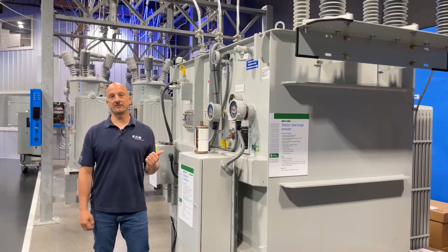So this transformer is 5,000 kVA, but it also has a slash rating 6250. And that's because we have fans and radiators on the back to cool it down so the oil can move through those radiators and we get more kVA out of the transformer. That's going to come into our calculations for full load amps and also our fault current a little bit differently, so we have to think about that. This one has 34.5 kV in, 13.8 kV out.